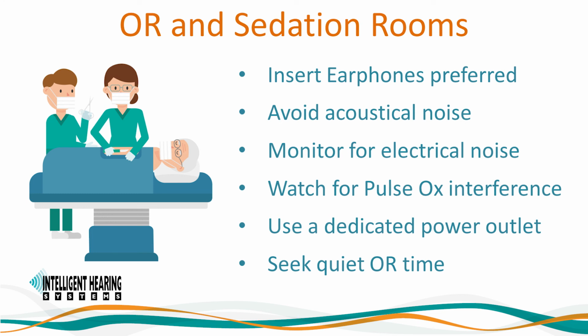And if it does, then negotiate with the anesthesiologist to do without if possible. If a pulse oximeter is used, position it as far away from the patient and equipment as possible. Place at patient's feet end. Run oximeter on battery if this eliminates interference and is available.